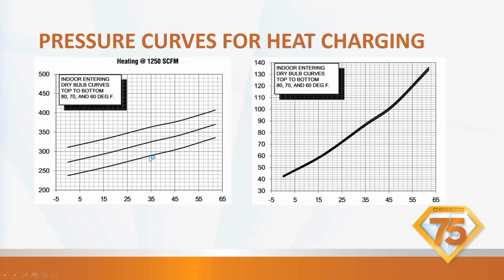So we're going to go up to the center one, 70 degrees, and then we're going to go straight across to the left. So our high side, when charged properly and when our airflow is correct, is going to be about 330-ish. And then on the low side, we're going to go over to 35 degrees, come up to the indoor temperature, and come straight across, and our suction should be around 88-ish.